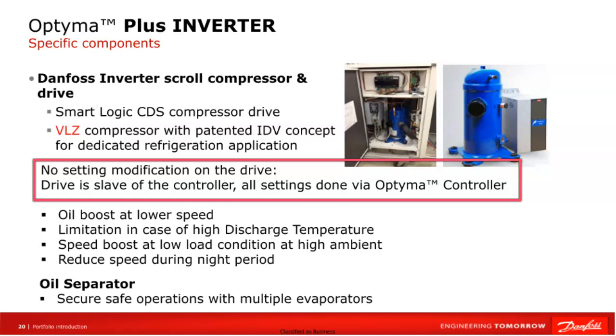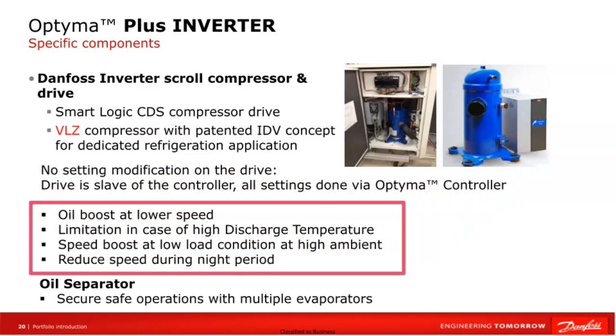The controller also serves to protect the condensing unit by implementing various safety functions such as increasing the quality of compressor bearings lubrication at low compressor speeds, protection of the unit when the discharge temperature reaches too high a level, adjusting the compressor speed in response to a low load at a simultaneous high ambient temperature, limiting the compressor speed in night mode.